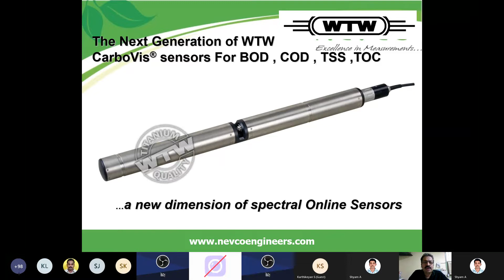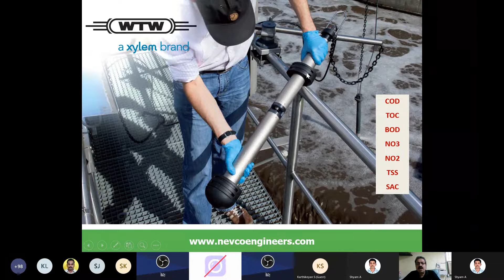Then we have the measurement of BOD, COD, TSS, and TOC. This is called the main probe, which has a built-in spectrophotometer. You can see this. It can be chain-hung directly. You can have a hanging position and put it in the effluent directly. And it has a small one here for shockproofing. They are both provided. If it falls down, it will not be damaged. There is also another shockproof protection system given here. If it falls on its side also, it will save the electronics from damage.